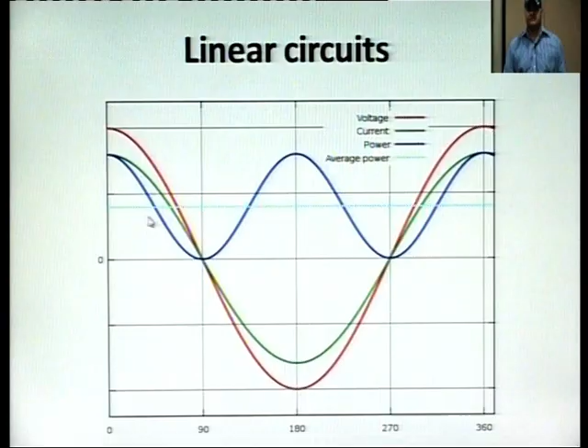Now we will discuss what real and reactive power are, and the difference between the two. The real power performs actual work, such as heating a burner element or illuminating an incandescent bulb. But the reactive power does not perform work; it energizes the magnetic fields in motor windings or in power supplies, which create the inductive loads.